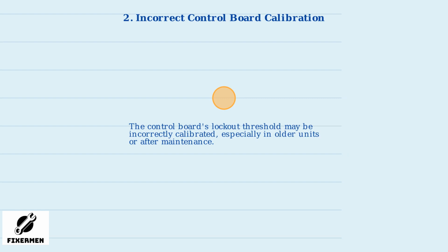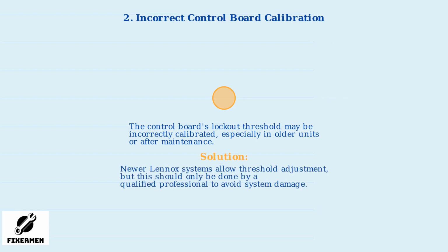Another common cause is incorrect calibration of the control board's lockout threshold. The programmable logic that sets the temperature limit for lockout might be misconfigured, particularly in older units or after maintenance work. This can lead to premature lockouts even in moderate cold.